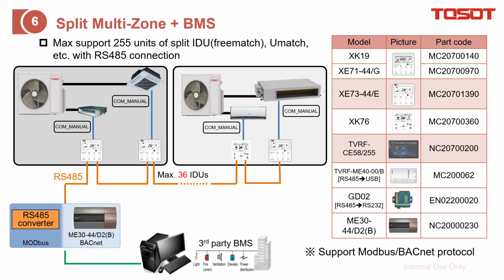BMS for free match. First, from this diagram, you can find that in this case there are just 2 free match systems. We just need to apply the wired controller as an adapter to change the signal from the indoor unit, then output the Modbus with RS485 connection. The circuit from the indoor unit PCB is the COM terminal.